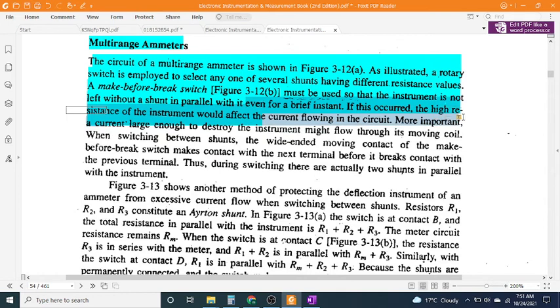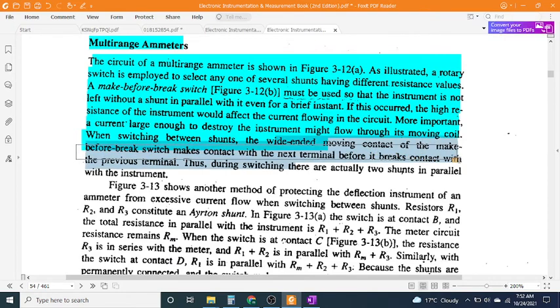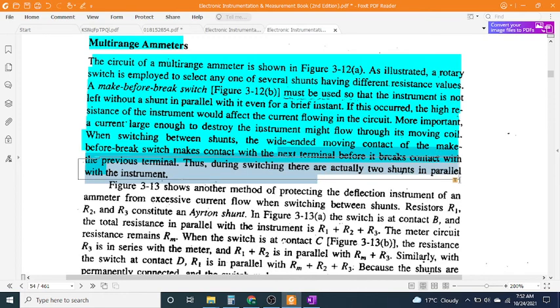More importantly, a current large enough to destroy the instrument might flow through its moving coil. When switching between shunts, the wide-ended moving contact of the make-before-break switch makes contact with the next terminal before it breaks contact with the previous terminal. Thus, during switching there are actually two shunts in parallel with the instrument.